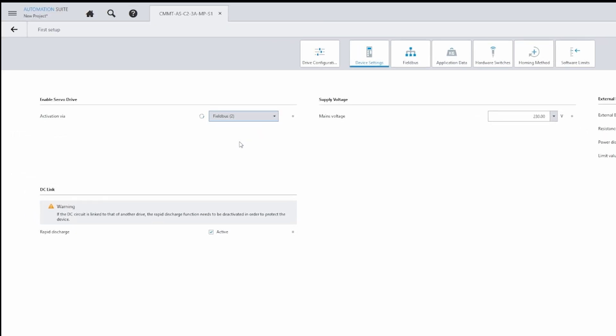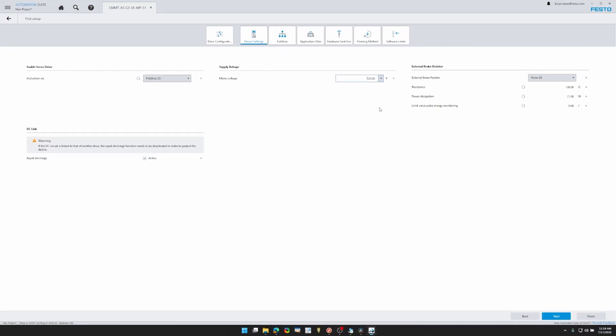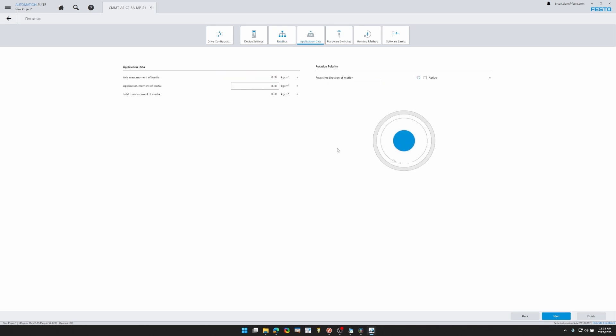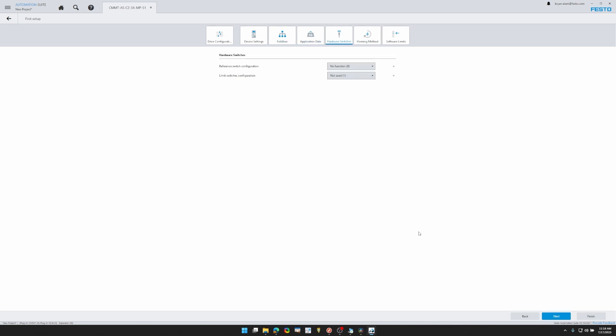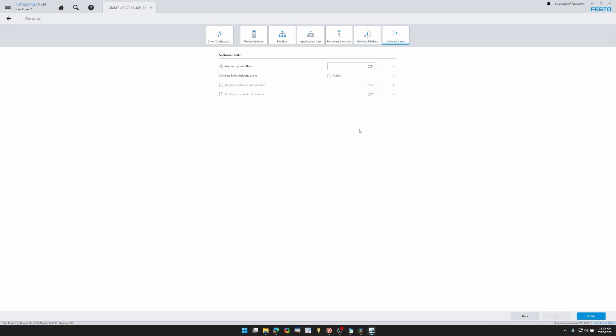Activation, I'm going to set it to field bus, mains voltage 120 since I'm using wall power. Next, here you can see some different field bus protocols. Set your application data, such as the mass. If you had hardware switches, you could put in some hardware switches there, configure those. Here's the homing method section. We have lots of different homing methods that you can select from. Here's the software limits page, which you can activate or deactivate. This can be activated or deactivated in TIA Portal as well.